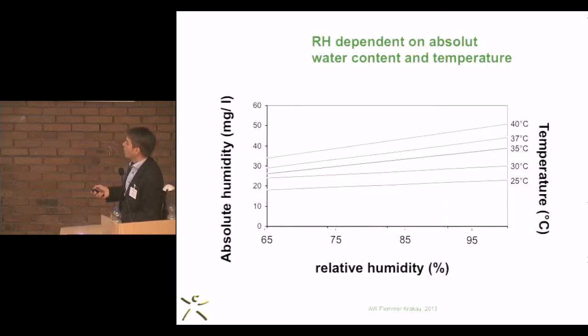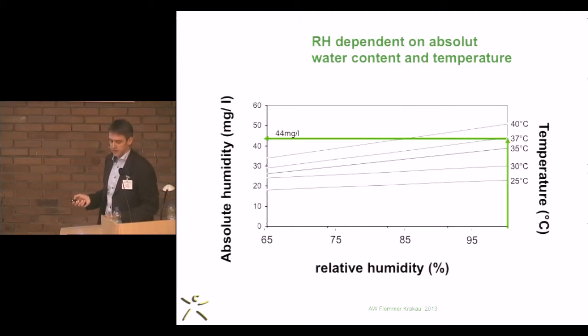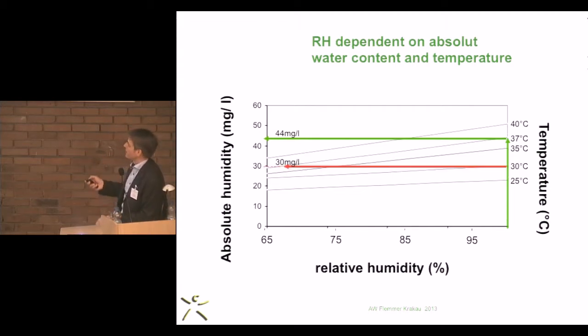Good. Let's continue. Now, when we have a heated humidifier, what we usually use, we would like to achieve 100% relative humidity at 37 degrees Celsius, equaling 44 milligrams per liter of gas. So that's normal. Now, we have to keep in mind that once air that is conditioned to 100% cools down, it loses automatically some amount of water. For example, if we cool air down to 30 degrees Celsius, then the maximum humidity you can achieve at that temperature is only 30 milligrams per liter. Once you reheat this gas, you're not going to achieve 100% at all if you don't add additional humidity. You end up with a relative humidity then of only 65%.